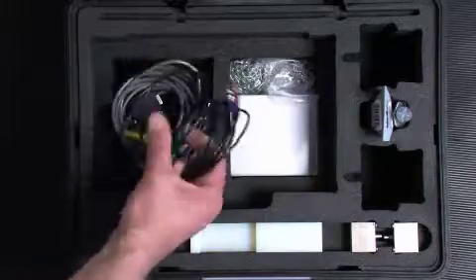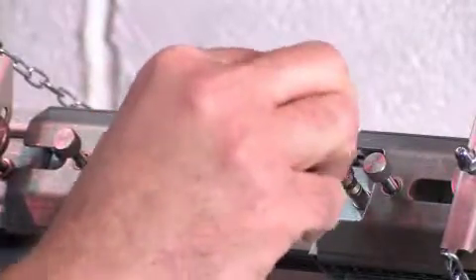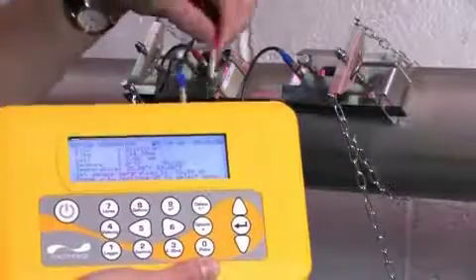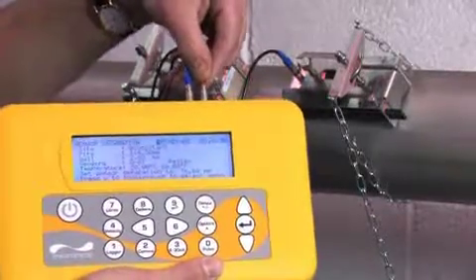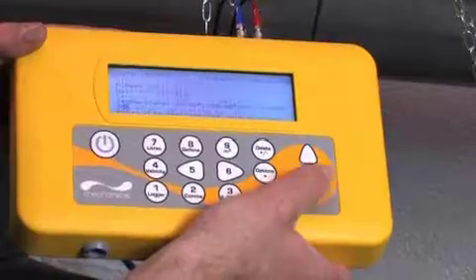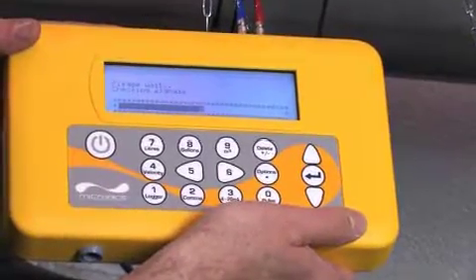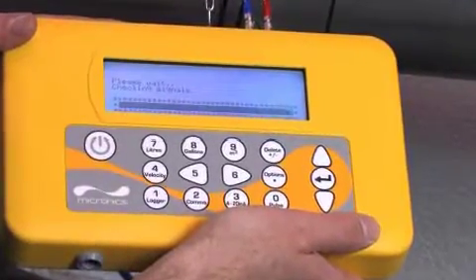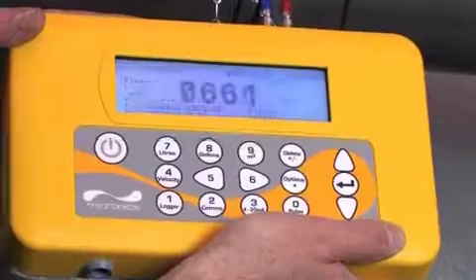Once the sensors are installed, connect the blue cable to the downstream sensor in the flow meter and the red cable to the upstream sensor in the flow meter. The successful installation of the cables and sensors means that once you press the enter button again, the flow meter will search for the best signal and begin to measure the flow.